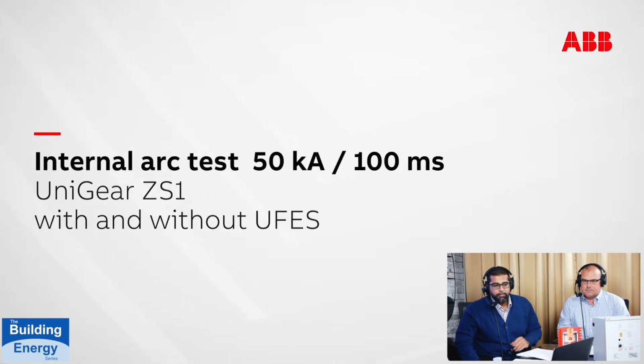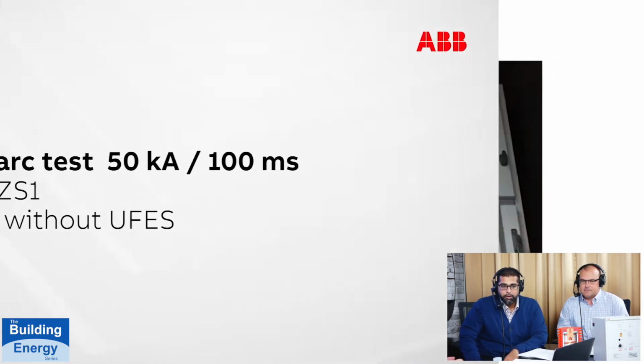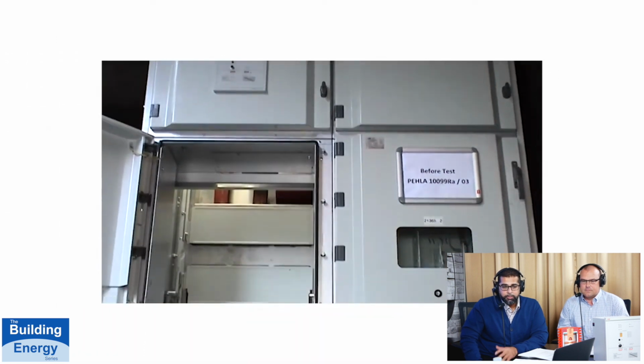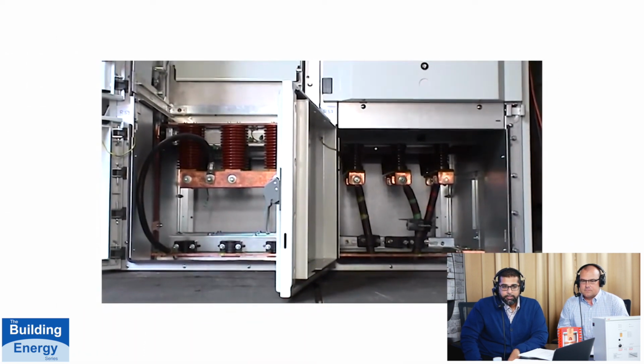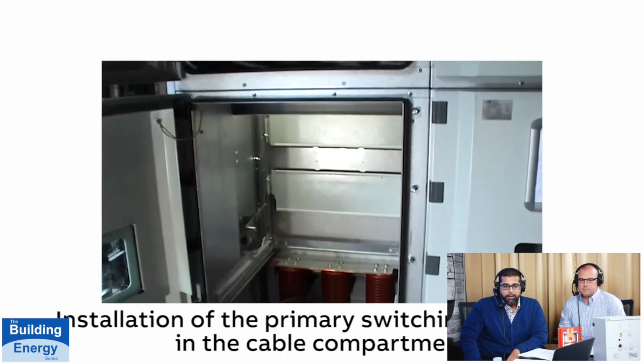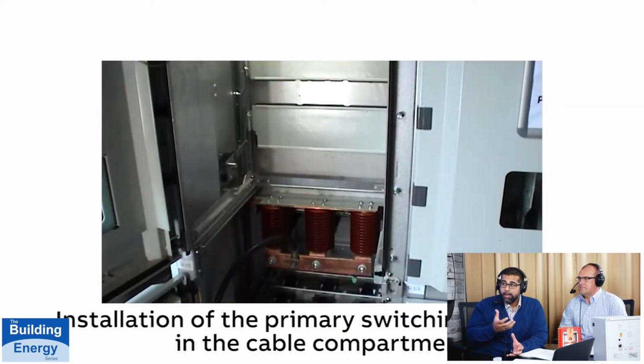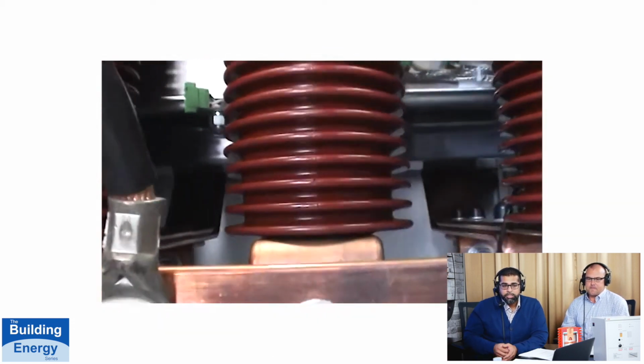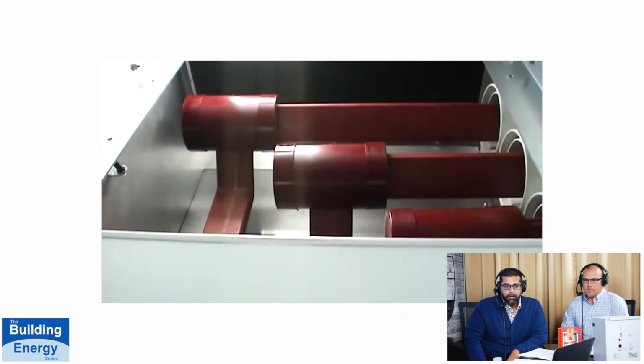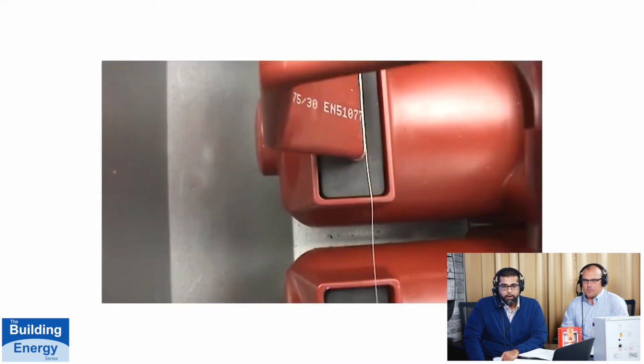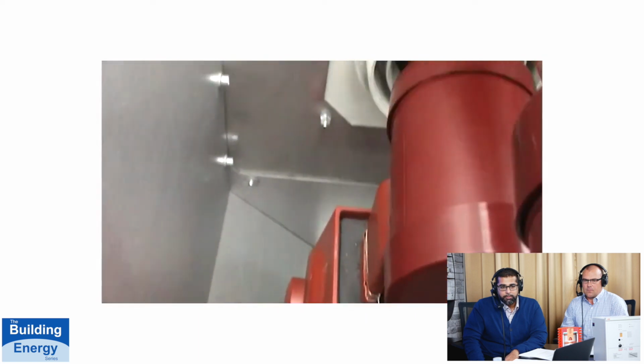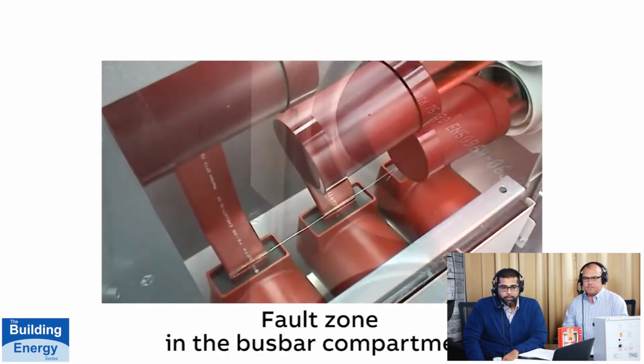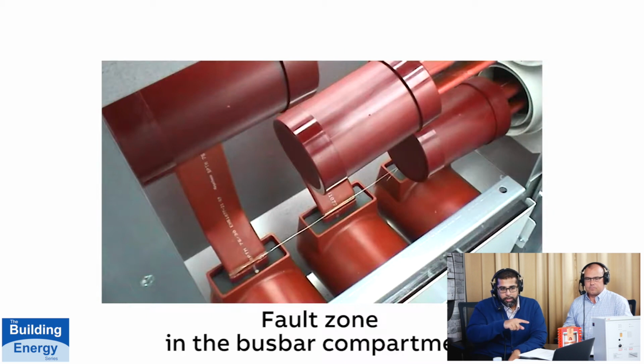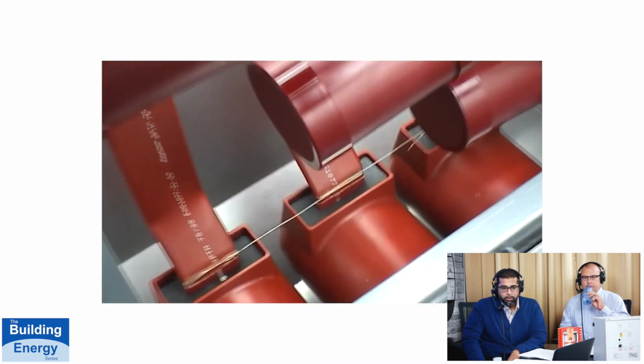That's right. So getting into the equipment side, you touched on it a little bit as well. This was a test that we conducted inside ABB at 50 kiloamps for 100 milliseconds only, between switchgear that has the ultra-fast earthing switch installed and that which doesn't. It shows the amount of destruction that can take place inside your switchgear within just a matter of 100 milliseconds. You see here, the primary switching elements are connected to the main bus bar. They've simulated a three-phase fault between the bus bars. You see that little wire that's connected to all three phases.